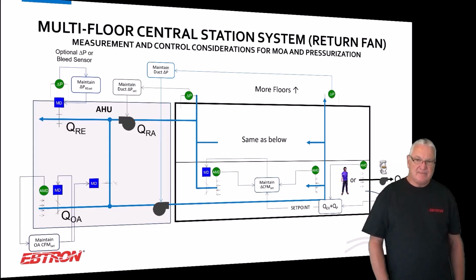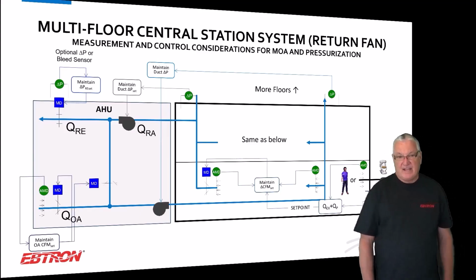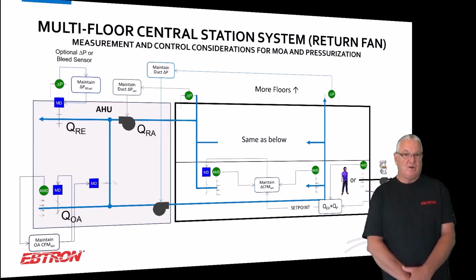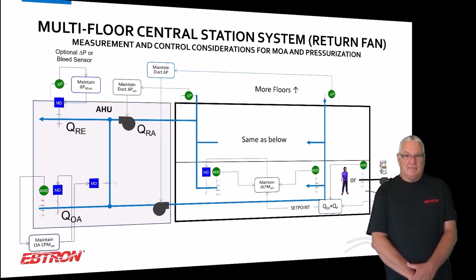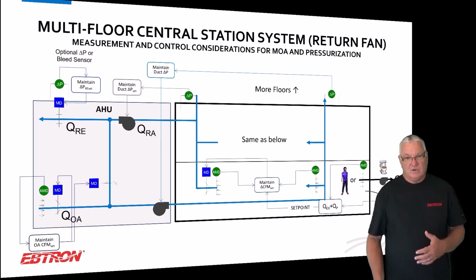Boy, a lot of times I can't get people to think this way. We have an air handling system serving 20 floors or something, and we're doing flow control, and we're ignoring 10 or 20 floors of stack pressure. I'm not a fan of ignoring that. The return air duct is a big hole in the building, and if you don't have a way to measure the ins and the outs on each floor, I think you're going to have stack pressure issues. Somehow you're going to have to compensate for that, and so we like to see you measure the total supply on the floor and the total return off the floor.